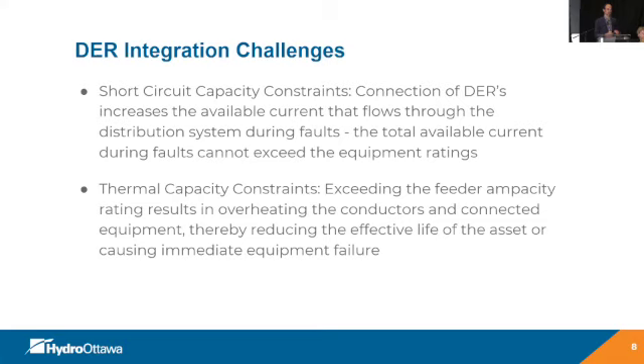As we connect more DERs to the system, they cause more current to flow through, and if there's a fault condition, those currents from the DER can now feed into the fault, which can exceed equipment ratings and cause failures. We have thermal capacity constraints as we add more DERs on the system, and now there's more ampacity flowing through the existing infrastructure. We can start to overheat the conductors, we can start to overheat equipment, and you can reduce the effective life, but you can also cause premature or immediate failure of equipment.